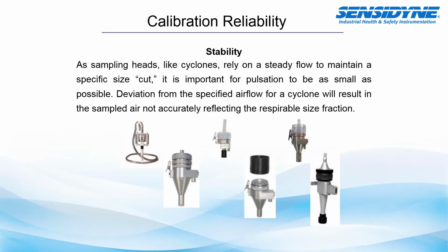Now, why is this important to me, or why do I care about the stability of my pump? Well, as sampling heads like cyclones rely on a very steady flow to maintain a specific cut size, it is important that pulsation be kept to as little as possible. Deviation from the specified airflow for a cyclone will result in the sampled air not accurately reflecting the respirable size fraction, or the thoracic size fraction, or the inhalable size fraction, depending on which type of device you are utilizing. The further that you move away from the manufacturer's required flow rate, you can either undersample or oversample, and therefore you would not have a representative size-selective sample.